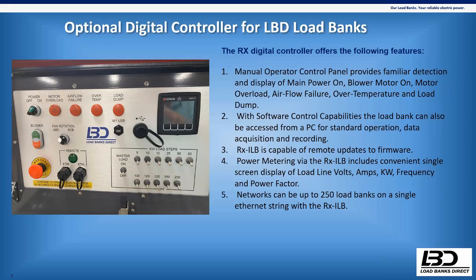That's really nice because sometimes you don't need all the bells and whistles. You just need a manually controlled load bank for whatever generator you may be testing that day. So it can keep things a little bit simpler than, for example, the ECU style controller. Everything on that one is done through the digital controller itself with soft key push buttons, whereas on this, you can come out and flip your load step switches, just like a standard manually controlled unit.